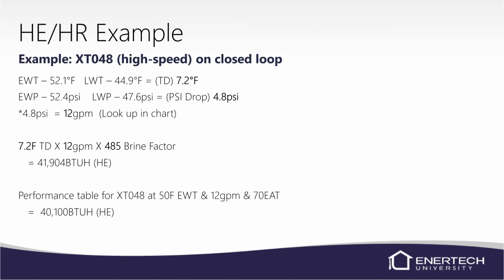So we'll go through some examples of heat of extraction, heat of rejection. Here's an XT048. Again, make sure we're in second stage, closed loop. We've got entering water temperature of 52.1 and leaving water temperature of 44.9.